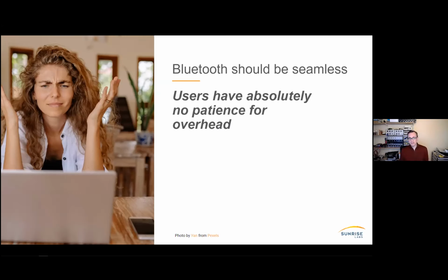Like I mentioned, the distinction between advertising and connecting. Do you persist a connection, or do you drop out to advertisement? If your device is one that has to talk with multiple different people, you may not want to persist a connection. But if you specifically don't want to talk to multiple people, if you're a patient-centric device, you may want to persist a connection. There's also power implications of persisting a connection versus not.